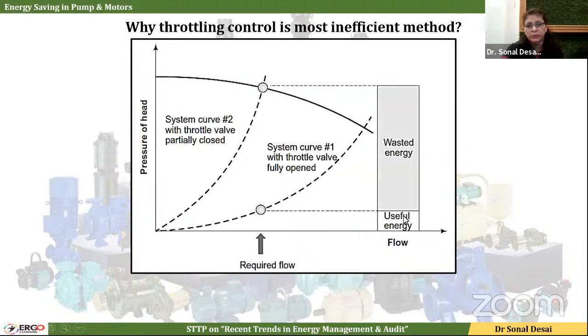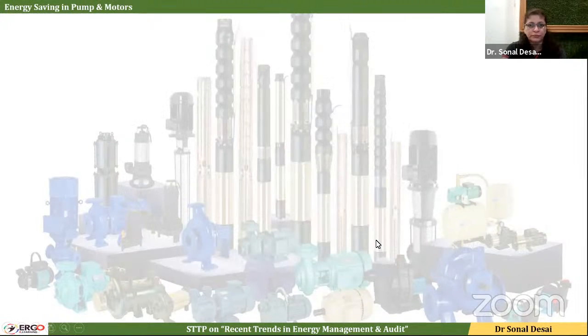When we operate the pump at this point, our useful energy is this. But when we throttle, what we are doing is reducing the flow from this point to this point. Initially the flow was this, now my reduced flow is this, but it has created undue head. If I have a two-story building and I'm pumping to a 40-meter height rather than 20 meters, those 20 meters I'm not utilizing. My overhead tank is just on the second floor only. So why should I pump water which is capable of reaching a four-story building? This is what happens when I select a pump of a larger size and then control with the help of flow. I'm wasting this much energy.